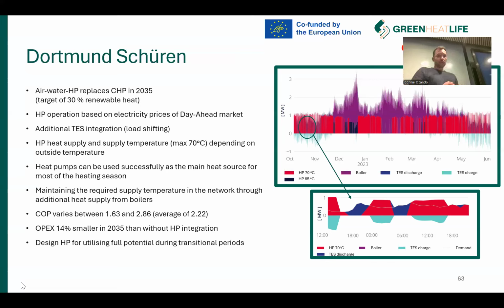So all in all, we showed that the heat pump can be operated for most of the year, even though we only have limited supply temperatures available. The heat pump can only supply heat at 70 degrees Celsius. And at lower outside temperatures, the supply temperature the heat pump can reach will drop a little bit. So we have to mix in boiler heat. The boiler will supply the heat so we reach the high supply temperatures of the network, around 90 to 100 degrees Celsius.